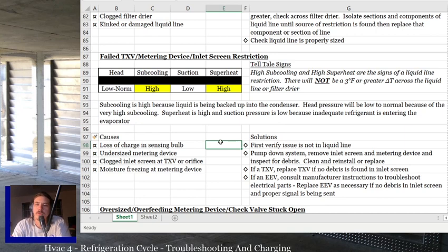But if you're pretty sure the metering device is fine, or you've got a piston, you could just clean out the piston or clean out the clog in the inlet screen, and you'll be good to go. Just look for this: if they didn't purge while brazing and you've got a bunch of black stuff in the inlet screen, if you clean that out, it'll probably be fine. And moisture freezing at the metering device. This isn't really the same thing, it's a whole other issue, but it could cause a similar looking problem. So just keep that in mind.